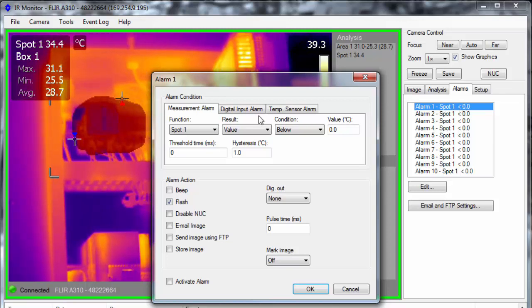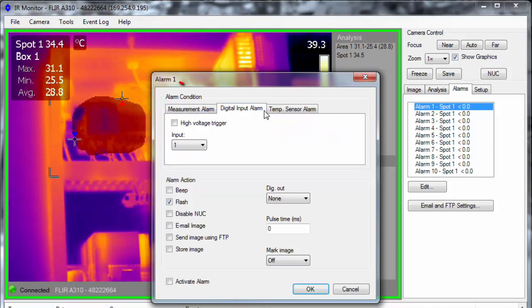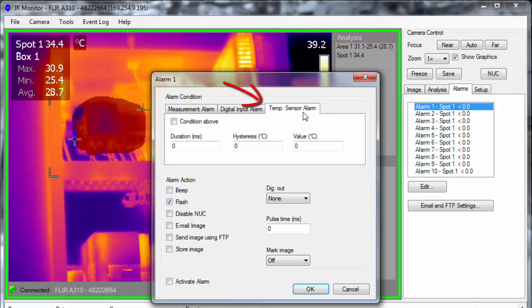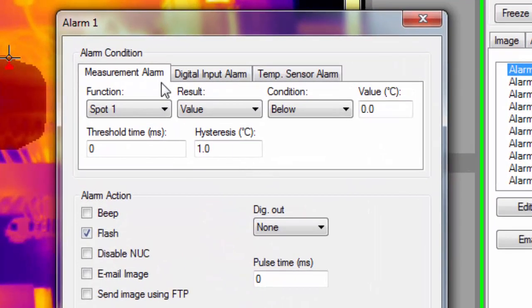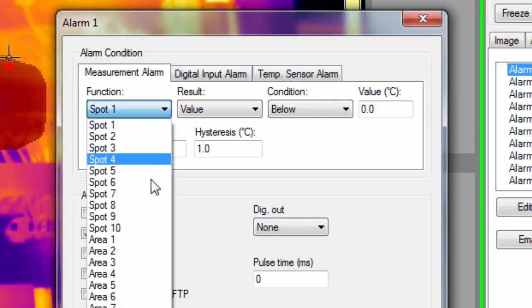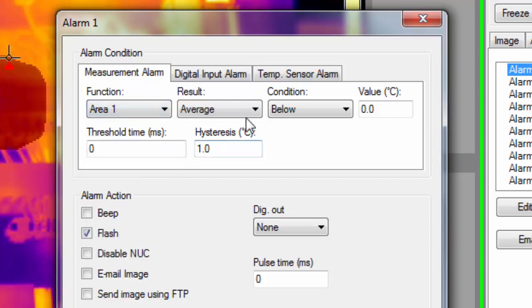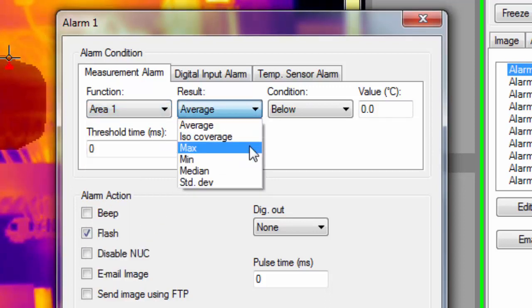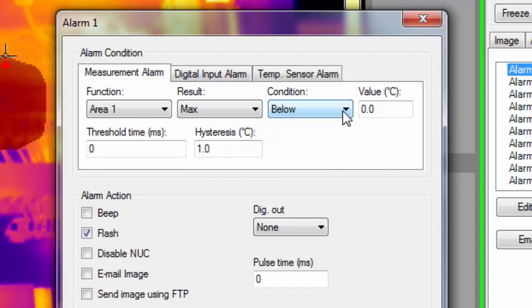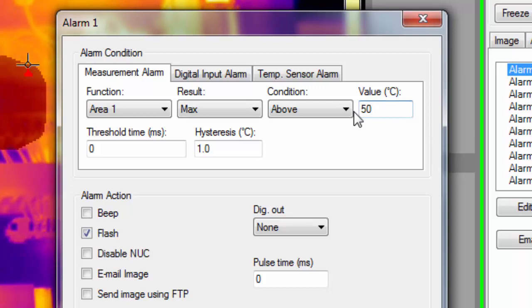Three different types of alarms can be configured: alarms based on a measurement tool value, based on a digital input signal, or based on the internal camera temperature. Here's an example of an alarm based on the max temp of Area 1. There will be an alarm if the temperature is above 50 degrees C for at least one second. The threshold time helps avoid false alarms.